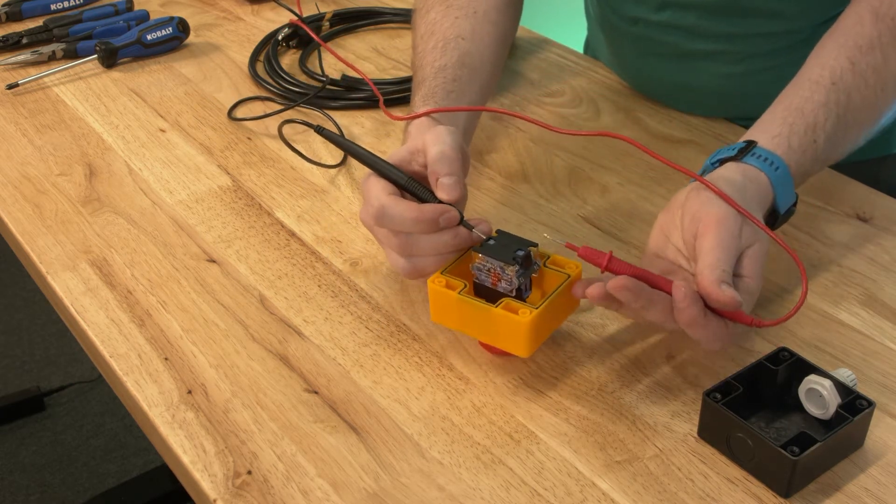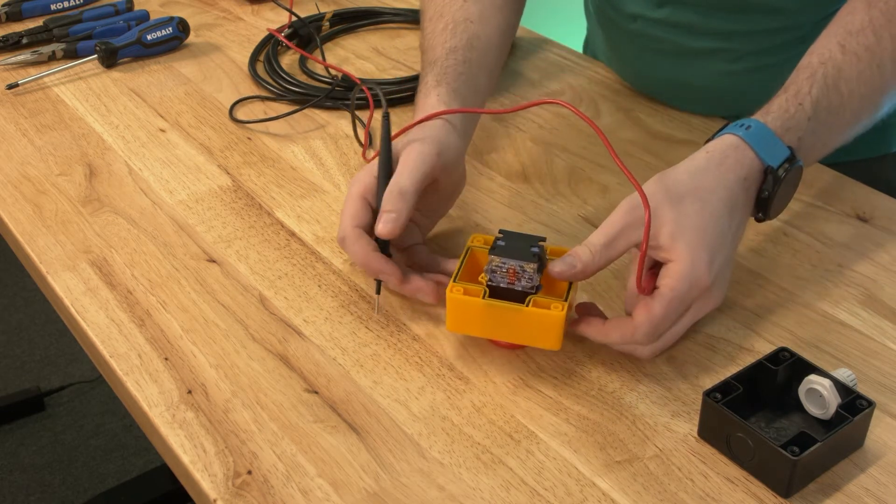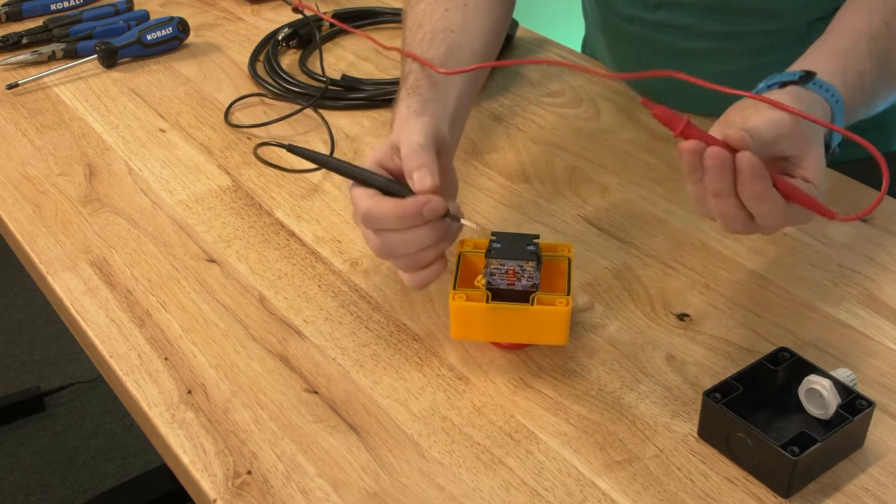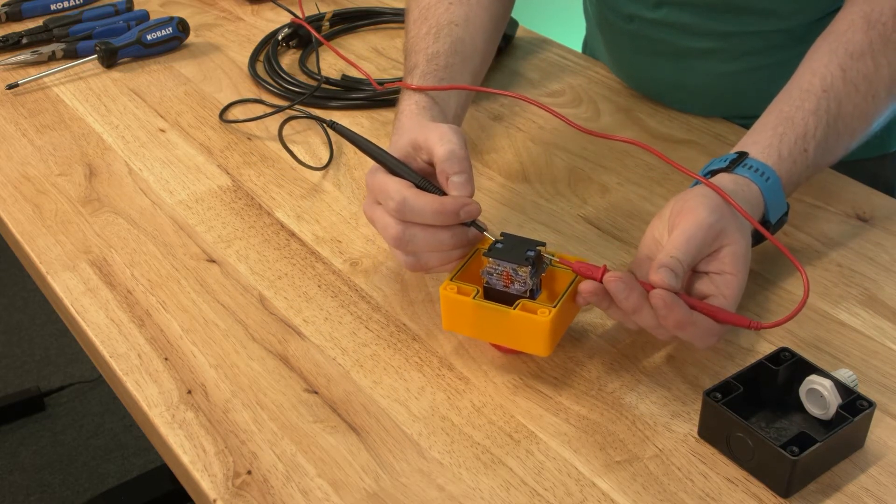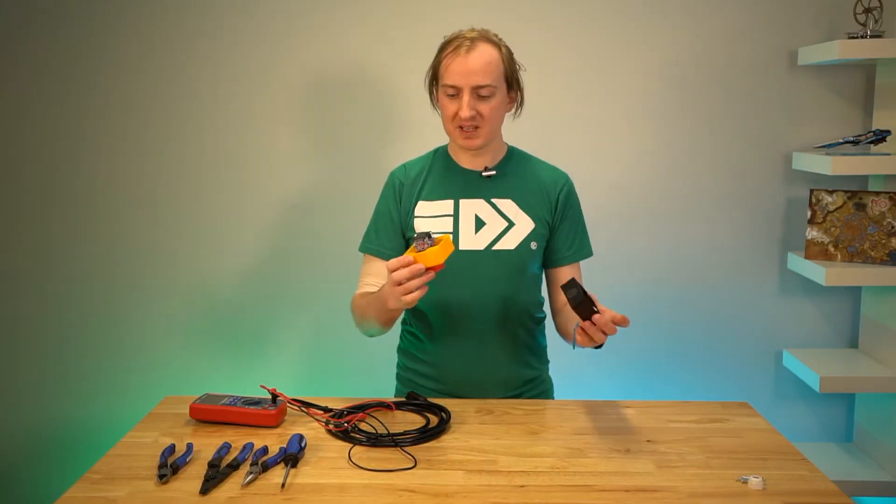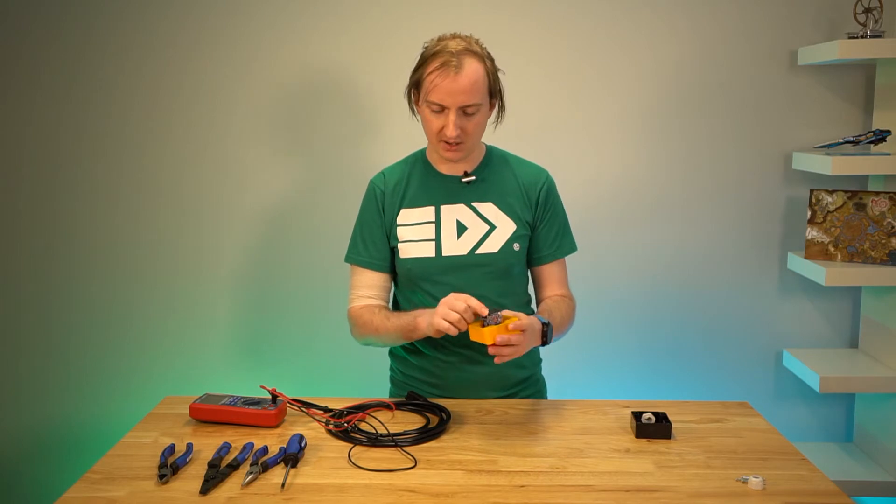And we'll verify that the two three and two four here are not. Again, push the button in. At this point, the number one contacts should be off, and they are. The number two contacts should be closed, and they are. So what that means is we verify we want to wire our live cable through the number one contacts.